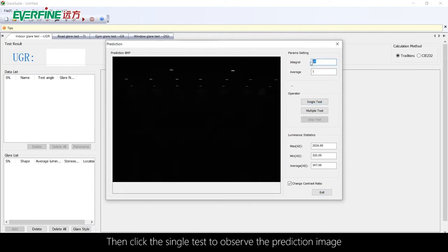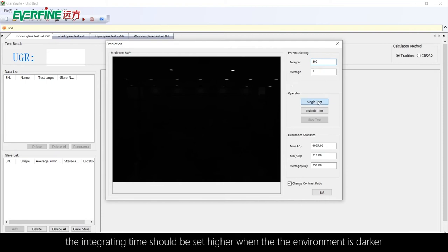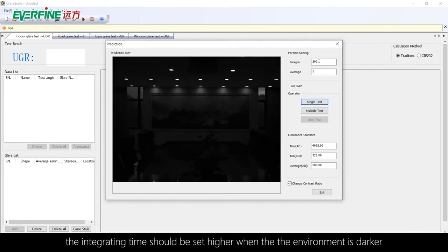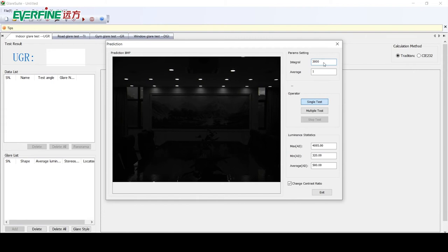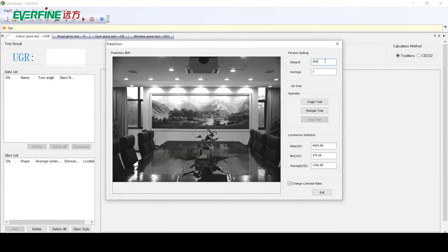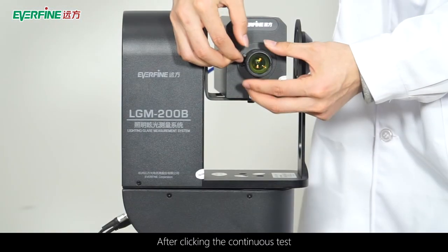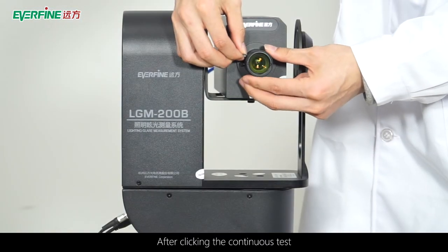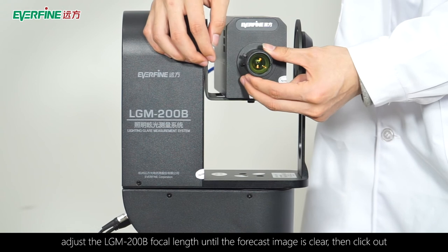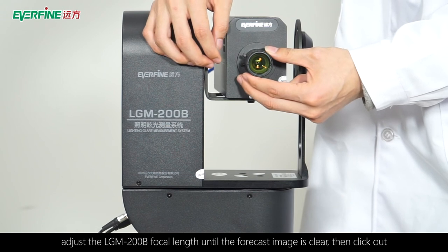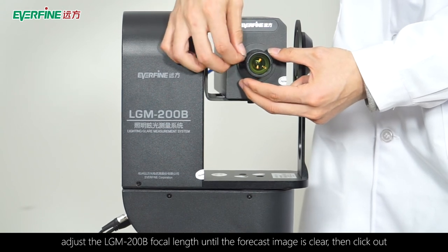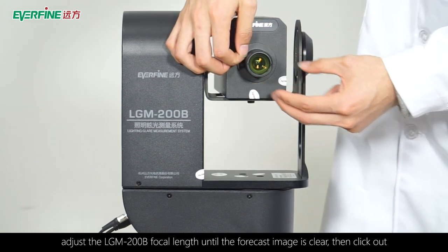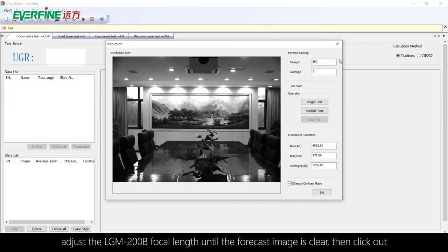Then click Single Test to observe the prediction image. The integration time should be set higher when the environment is darker. After clicking Multiple Test, adjust the LGM-200B focal length until the forecast image is clear, then exit.